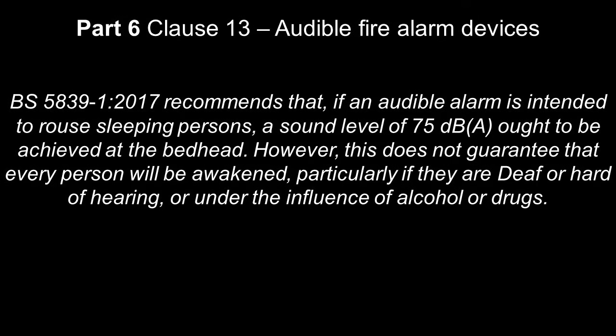So if we go to clause 13 on part 6, audible and visual alarm devices, it mentions part 1. Part 1 recommends that if an audible alarm is intended to rouse sleeping persons, a sound level of 75 dB ought to be achieved at the bedhead. However, this does not guarantee that every person will be awakened, particularly if they're deaf or hard of hearing or under the influence of alcohol or drugs. So what we do on Part 1 systems in commercial, hotels for example, generally speaking, 75 dB at the bedhead is what we record, and the reading we're looking for, and obviously we design systems to suit.